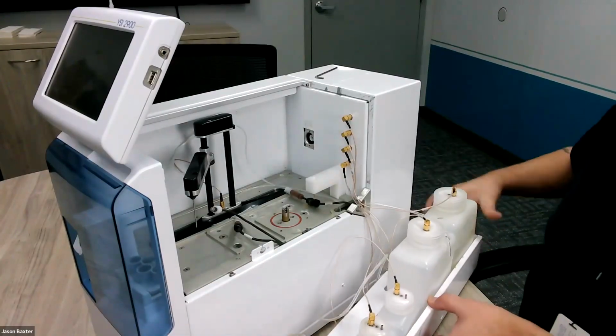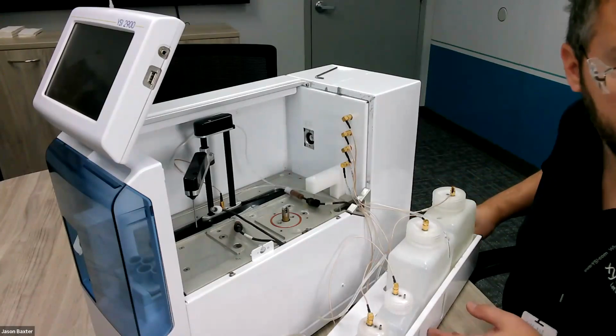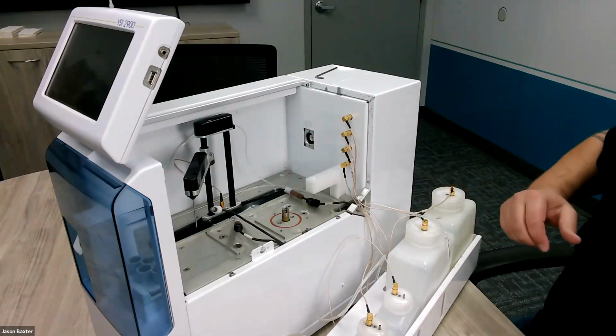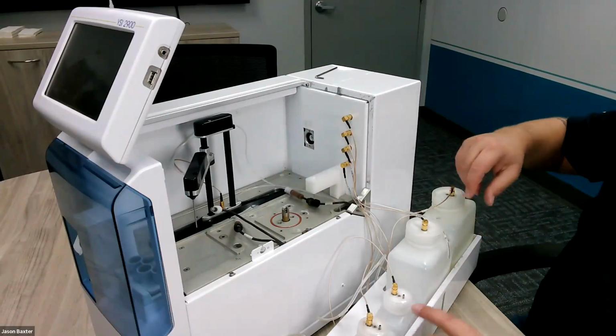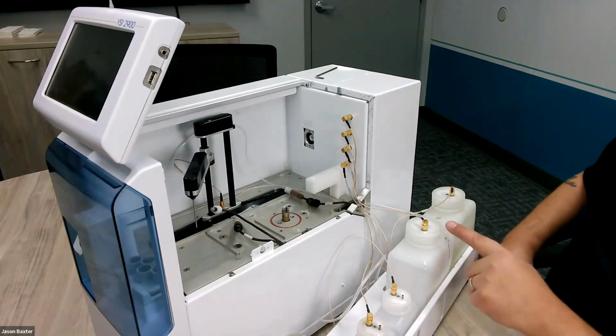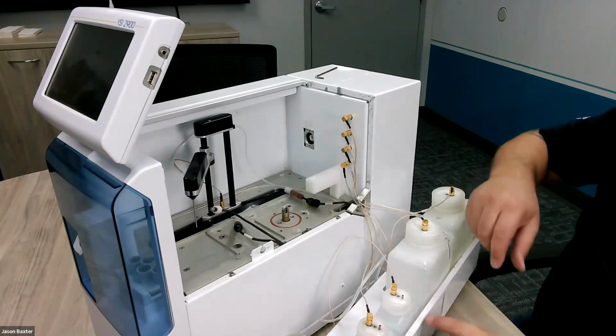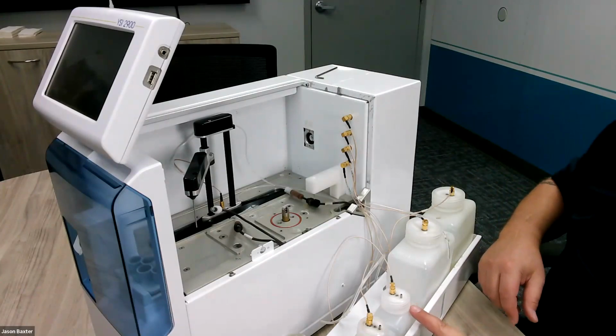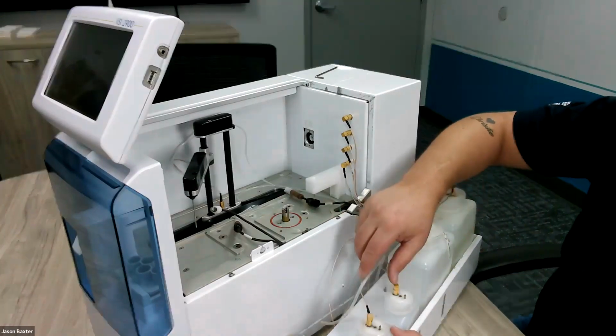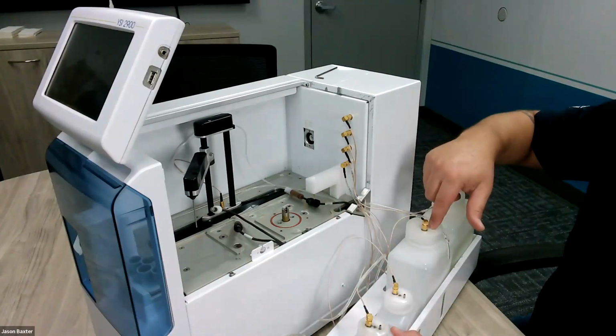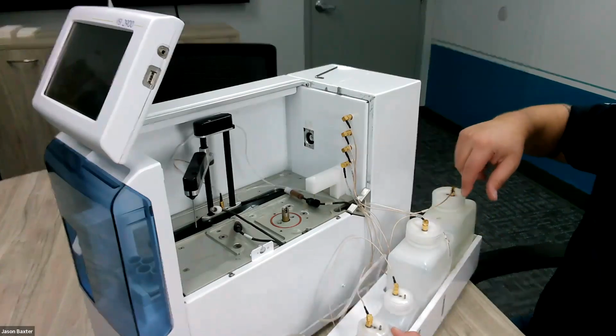Lastly, the part that confuses everybody is your bottle caps. To remove the bottle caps, you'll notice you have 2 here for the calibrator, 1 for the buffer and 1 for the waste. The 2 caps for the calibrator are identical, so I'm just going to take one apart instead of all 4. The buffer part comes apart the same way, the waste comes apart the same way.